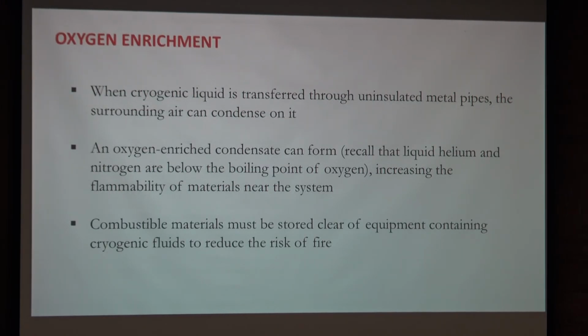Oxygen enrichment, we've already mentioned that. When you transfer cryogenic fluids or gases through uninsulated metal pipes, basically metal pipes that are on the outside in contact with air, then the oxygen in the surrounding air can condense on it, and that could create an oxygen-enriched environment.